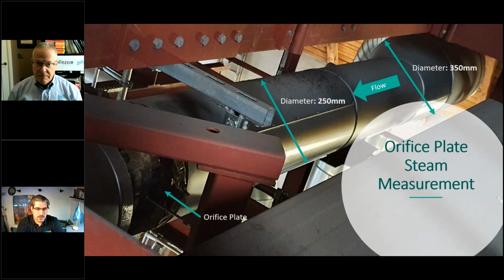So you now see the problem. You create steam in a big boiler, you have a big pipe, but then you need to turn everything down to another pipe diameter, to a smaller pipe diameter. And even inside the orifice plate, the meter's body is smaller, and the plate itself reduces the diameter again. So you probably have an opening of about 200 millimeters left to get all of your steam through.